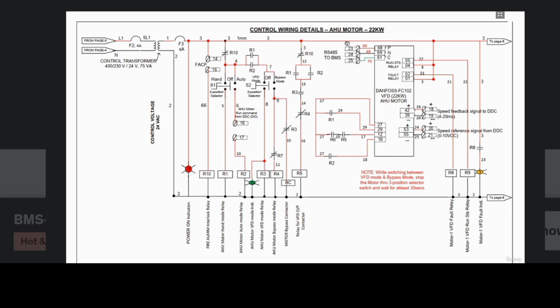Here we have terminals for the RS485. These terminals will be used for integration of the VFD to the BMS using Modbus or BACnet MSTP. Then we have terminals for speed control and speed feedback. Terminals 20 and 21 will be used to control the speed of the VFD, and then we will get the feedback on terminal numbers 18 and 19.